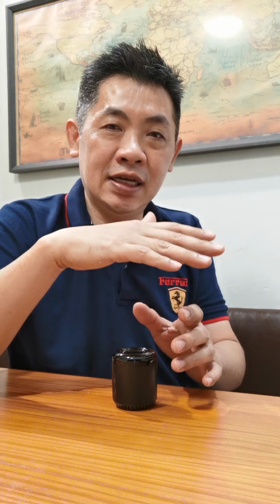Some of the technicians say that, oh yeah, you have lost half of your gas. That's inaccurate. That's very wrong. In fact, you have lost almost all of the gas, because whatever you lost, half of it will vaporize and try to balance this. When you start to see a pressure drop of about 50%, chances are you're left with so little liquefied gas that whatever is vaporizing is not enough to fill up the gap and cause a pressure equilibrium.